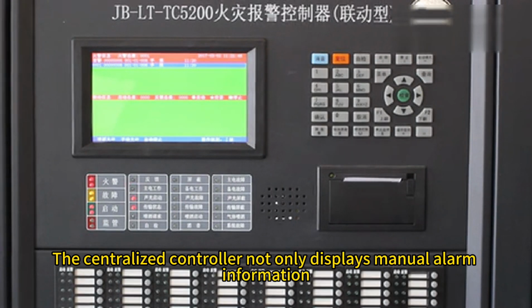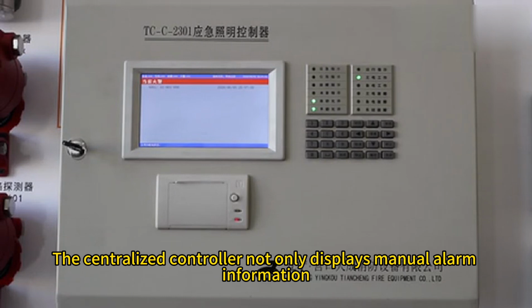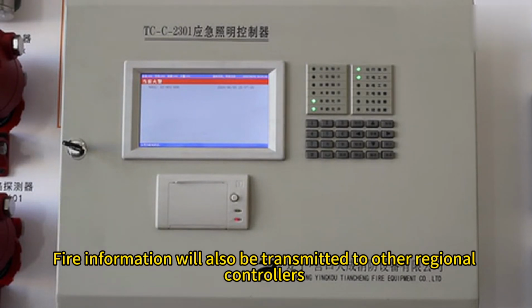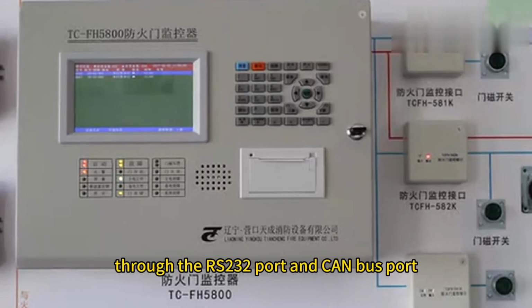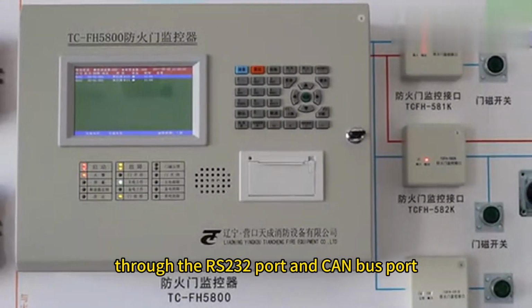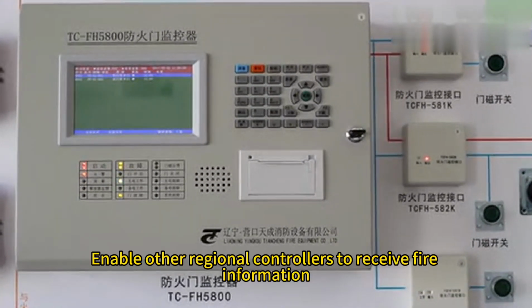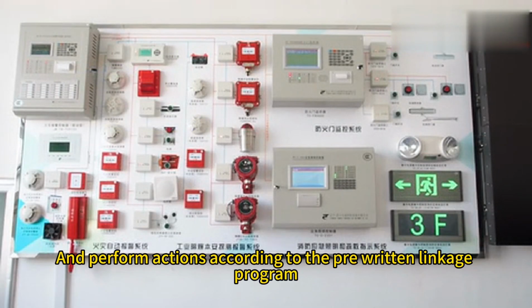The centralized controller not only displays manual alarm information, fire information will also be transmitted to other regional controllers through the RS232 port and CAN bus port. Enable other regional controllers to receive fire information and perform actions according to the pre-written linkage program.